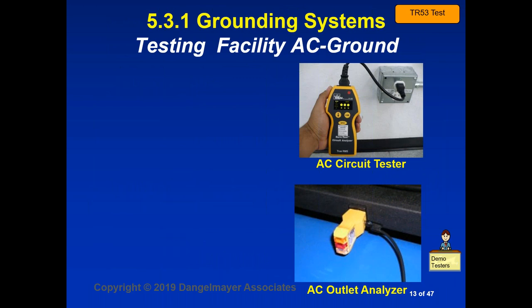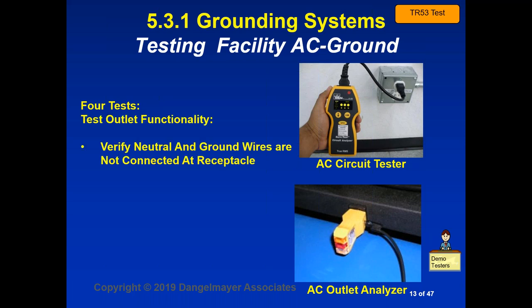So here you see some pictures of some of the testers that you can use to check your facility AC ground. We certainly recommend the AC circuit tester you see in the upper picture. The tester below will just test the power lines themselves, and it actually provides a convenient ground point for further testing. So, four tests. You're going to test your outlet functionality. You want to verify that the neutral and ground wires are not connected together at the receptacle. They should not be.